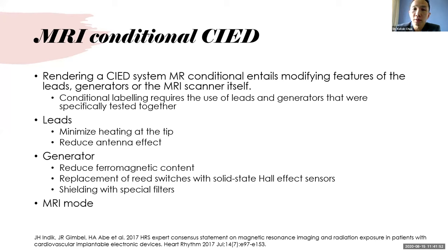For the leads, the two main challenges are to minimize the heating at the tip and to reduce the antenna effect. The heating at the tip can cause myocardial damage, pain, and changes in pacing and sensing function, while the antenna effect picks up resonant frequency and causes electric current to conduct and possibly myocardial capture, which can induce arrhythmias.